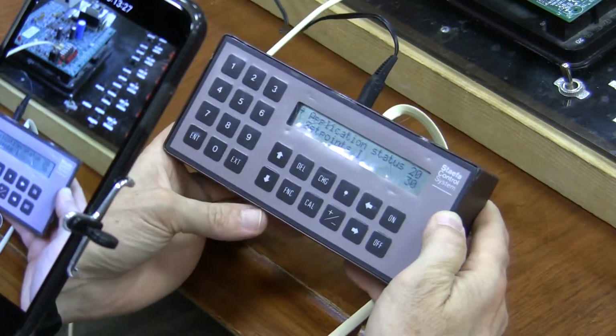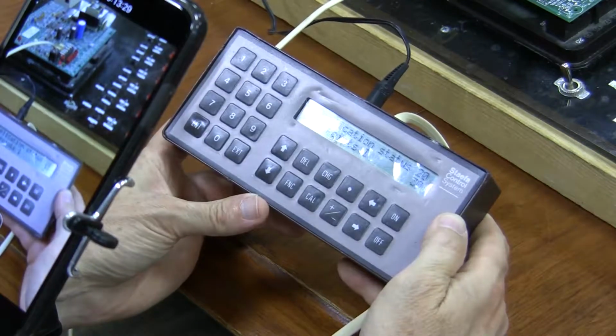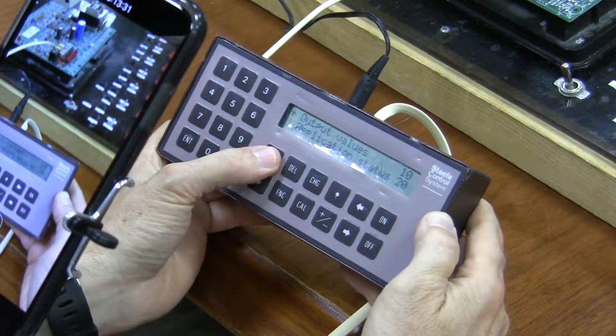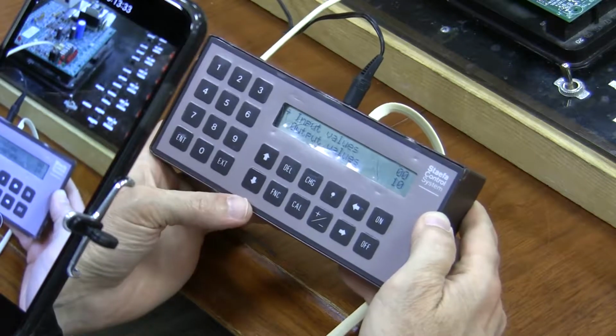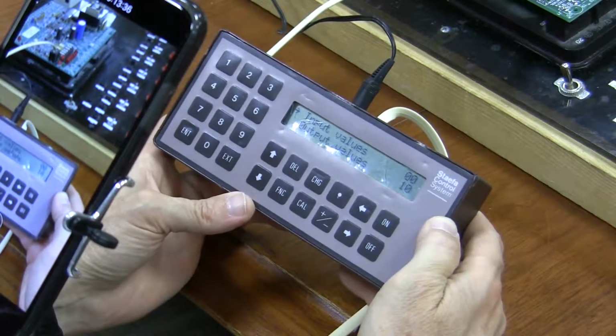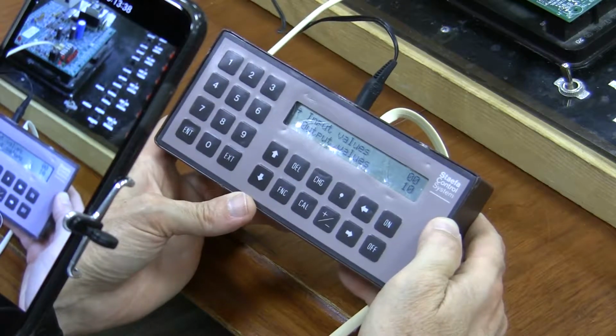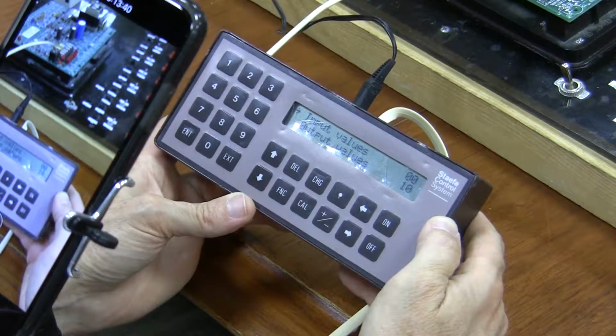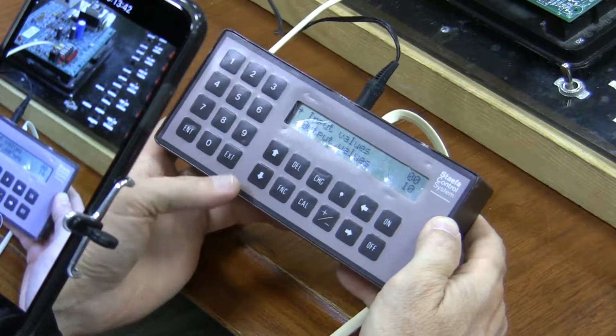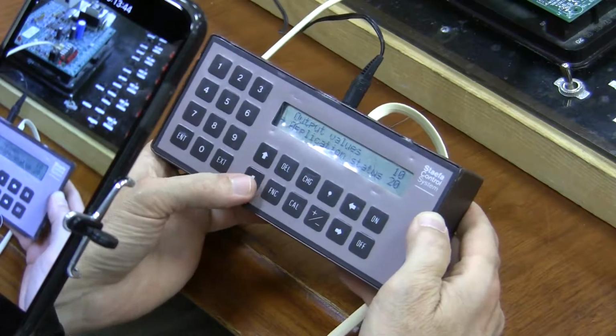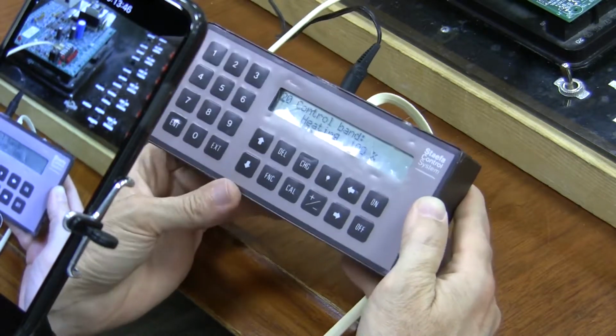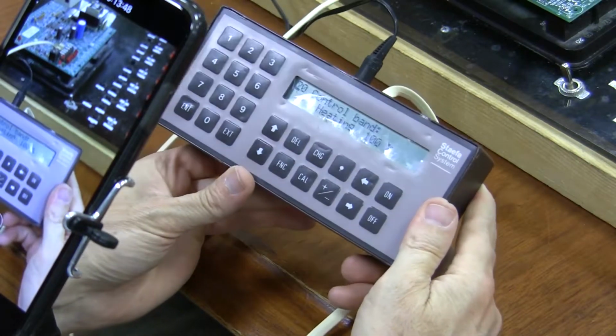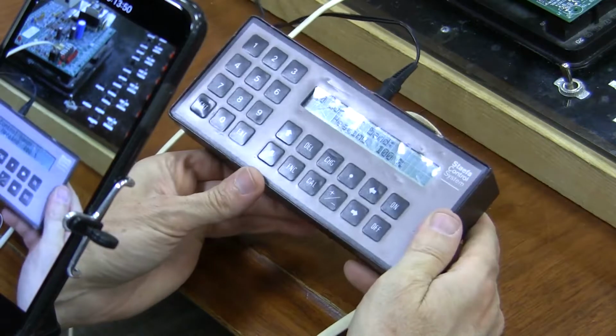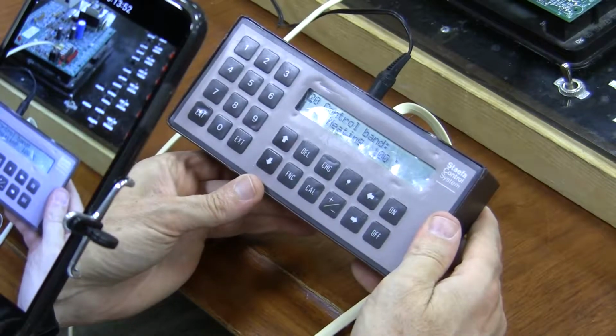We've talked about those two. Now here's the one that I really wanted to show you, this application status. So I'm going to back up here. Remember, I plug into the card, I come, and I'm here 0, 0, and I want to see what the zone temperature is. Then I compare it to set point. And then I think, well, it ought to be heating or cooling. If I come right here to this next parameter, application status, he comes up and tells me what he's thinking he's doing. In this particular case, this controller is heating 100%.